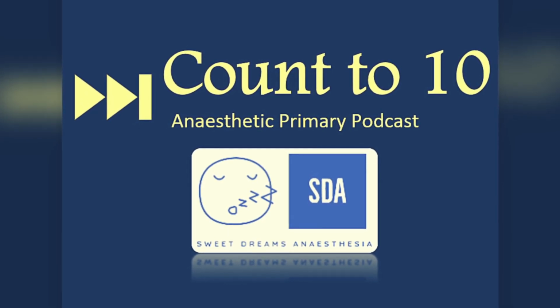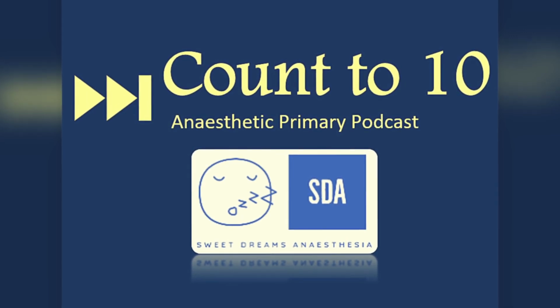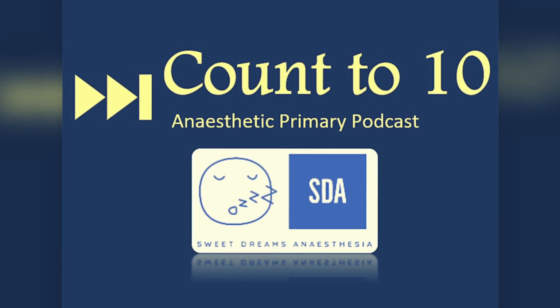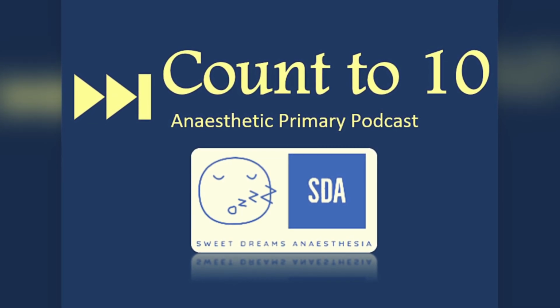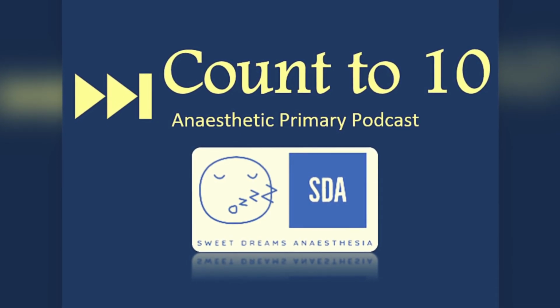And essentially what it's doing is measuring mouth and alveolar pressure. During normal respiration, the interrupter technique, as it says in its name, will interrupt breathing throughout a normal respiratory cycle. It'll interrupt breathing normally about every 50 to 100 mils, and it will measure the rate of flow before the interruption and after the interruption. It will measure the pressure at the mouth, and it will measure the pressure when flow stops. When flow stops, the pressure that's measured would be equal to the alveolar pressure. Then we will use Ohm's law again, and an equation will be rearranged to give us airway resistance.